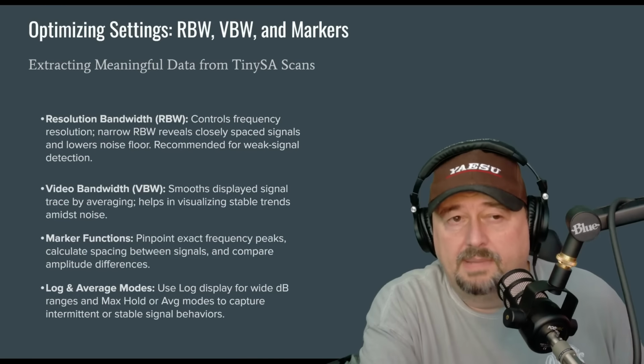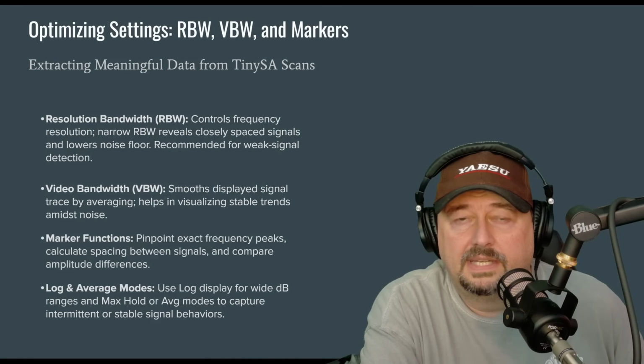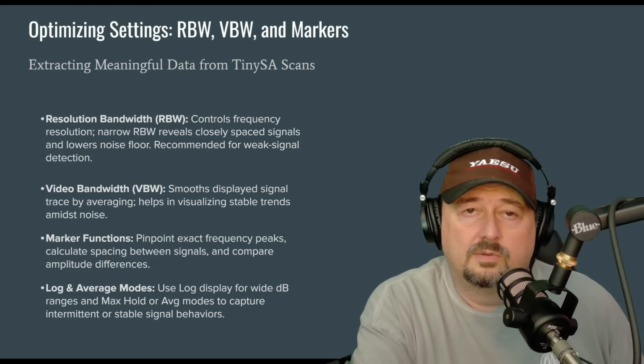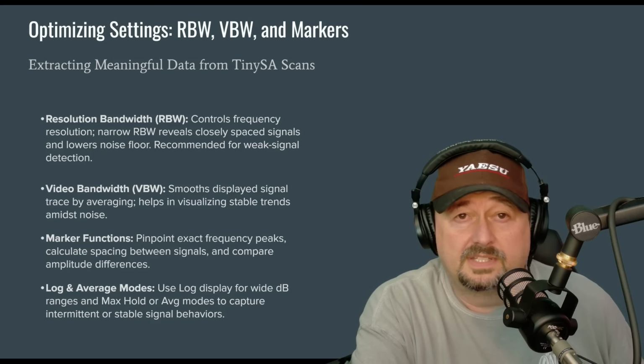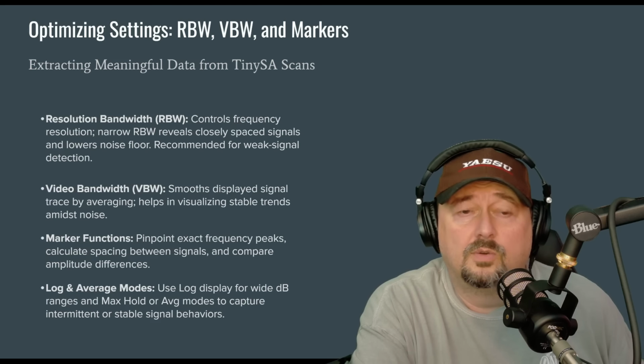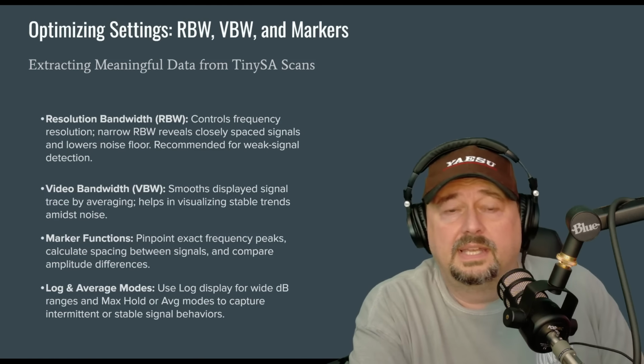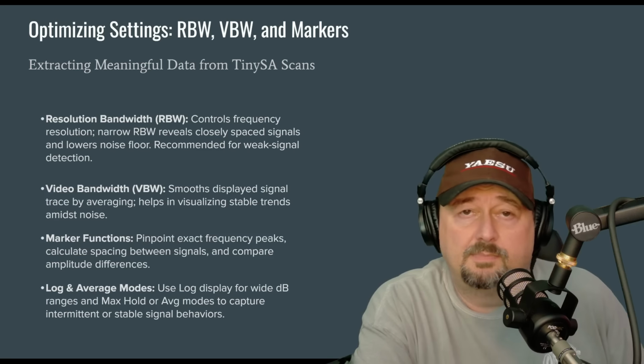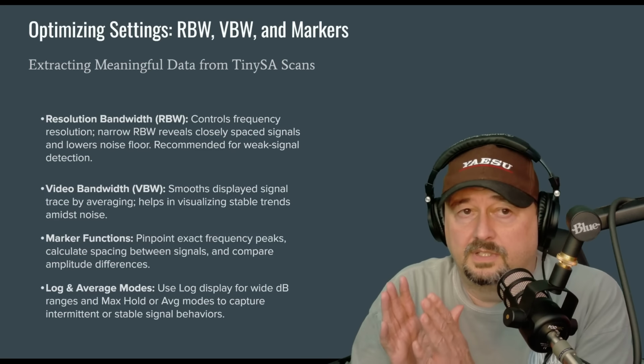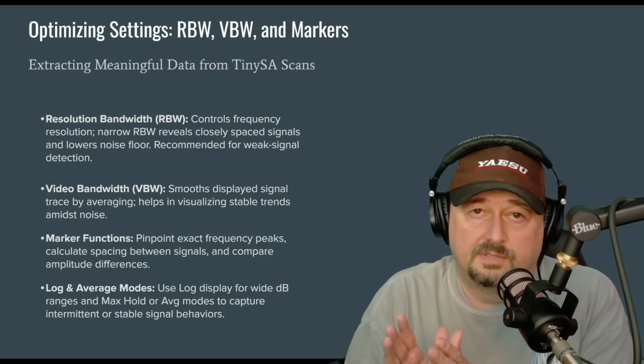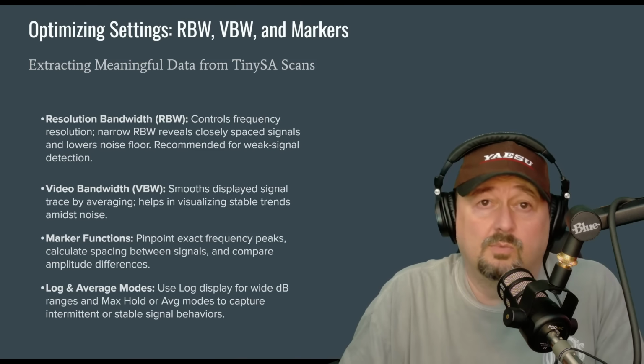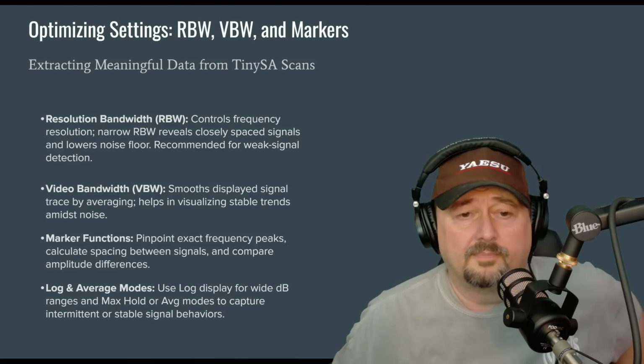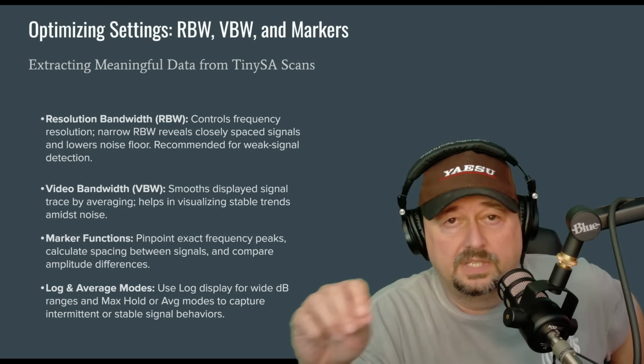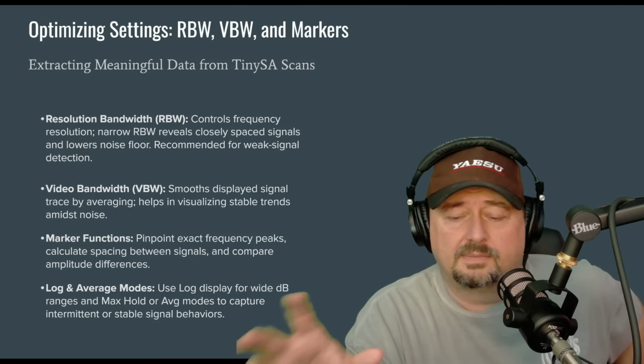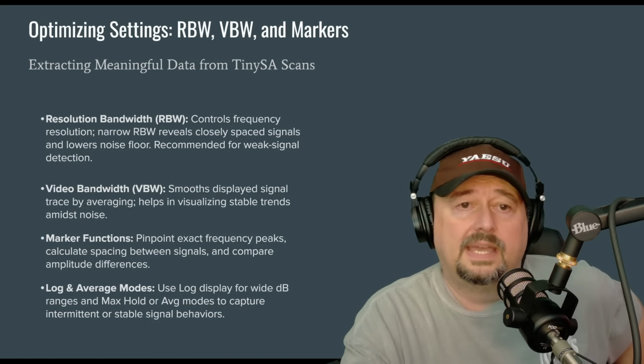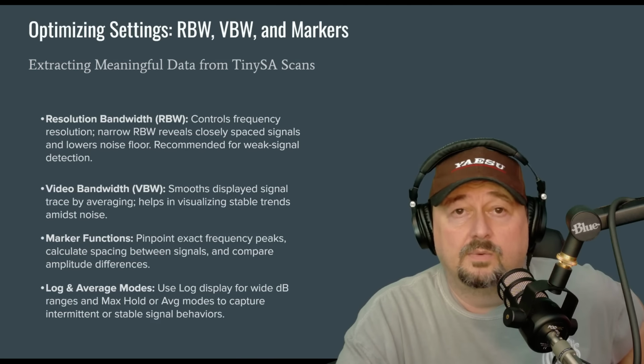So I just want to talk a little bit about resolution bandwidth and video bandwidth. Resolution bandwidth controls the frequency resolution. A narrow resolution bandwidth allows you to see closely spaced signals. So if you're looking at two signals that are really close together, by controlling that resolution bandwidth, you might see both of them, or you might just see one signal if the bandwidth is too wide. Video bandwidth is really smoothing of the display line. So sometimes when you're doing signal characterization, you have to adjust both of those to get exactly what you're looking for.